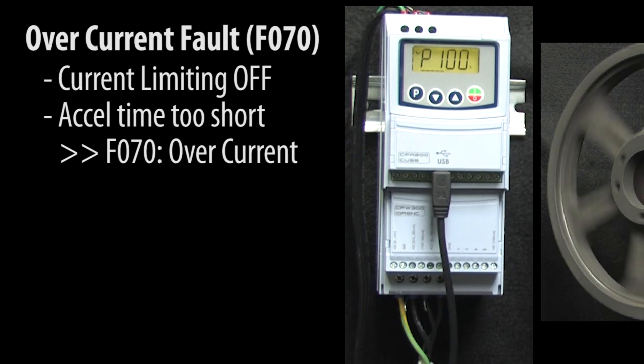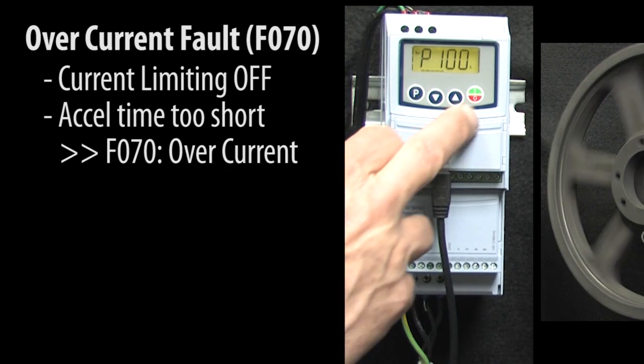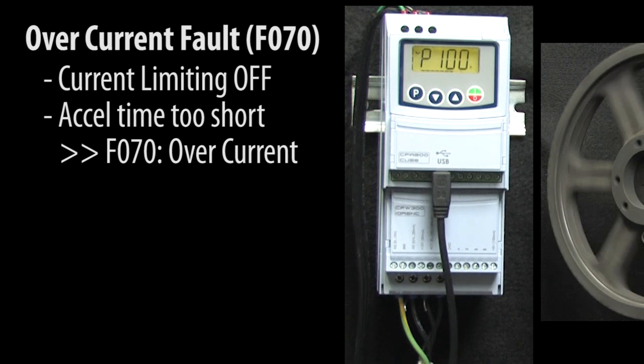So if you are getting an overcurrent fault under load, make sure the current limiting threshold is set to an appropriate value and the acceleration time is reasonable.